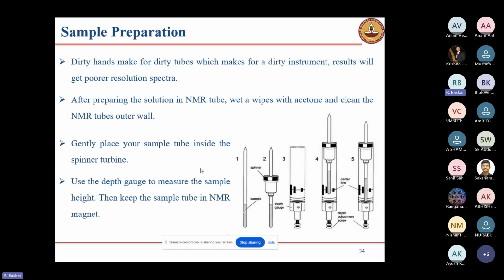If you are keeping it too high, your solution will not fill the homogeneous magnetic field. It will affect the shimming, and you will not get a proper NMR spectrum. If you are keeping it too low, it will go and hit the probe and the NMR tube will break. So we have to measure the height properly. This is called the depth gauge or measuring gauge. This is called the spinner, the sample spinner. This is the solution. If you prepare a smaller volume of solution, it will not fill the homogeneous magnetic field and the deuterium is also not sufficient for locking, so a lock fail will happen. So always prepare 0.5 ml of solution. If you make a higher volume, it will be fine, but deuterated solvents are very expensive.